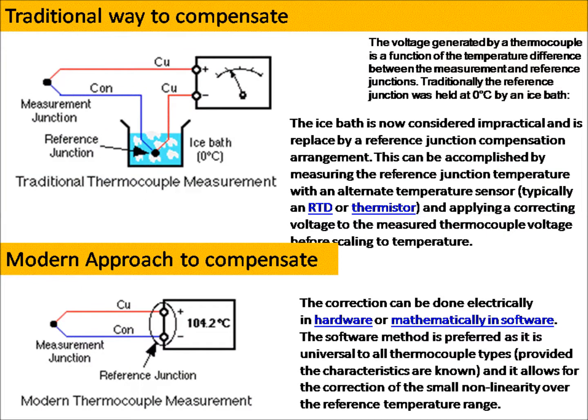Traditionally, the reference junction was held at 0 degrees Celsius using an ice bath. The ice bath is now considered impractical and is replaced by a reference junction compensation arrangement. This is accomplished by measuring the reference junction temperature with an alternate sensor — typically an RTD or thermistor — and applying a correcting voltage to the measured thermocouple voltage before scaling to temperature. The correction can be done electrically in hardware or mathematically in software. The software method is preferred as it is universal to all thermocouple types and allows correction of small non-linearity over the reference temperature range.